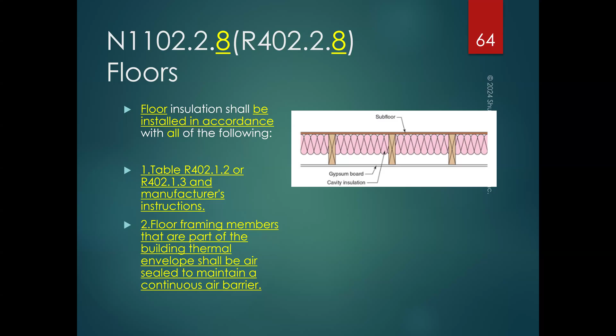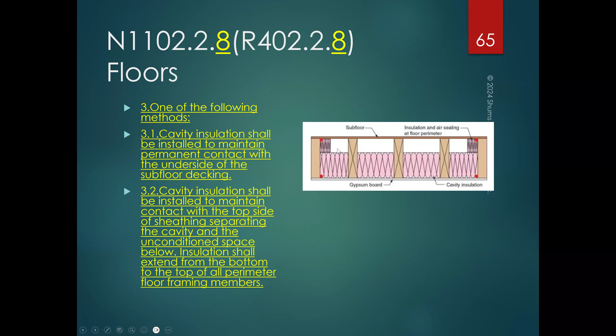Cavity insulation shall be installed to maintain contact with the top side of the sheathing, separating the cavity and the unconditioned space below, from the bottom to the top of all perimeter framing members. So this is what that's talking about right here. Gotta make sure it goes all the way up, all right? And then a combination of cavity insulation and continuous insulation shall be installed such that the cavity insulation is in contact with the top side of the continuous insulation.